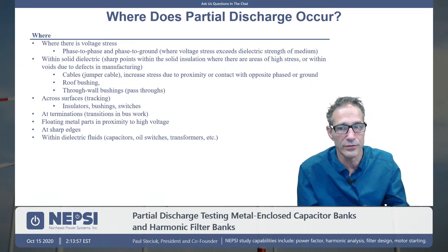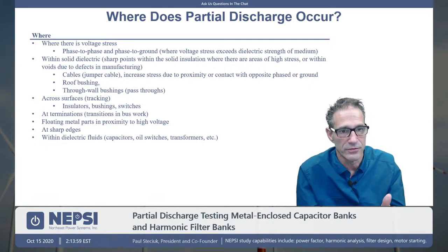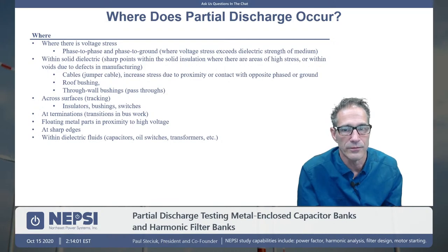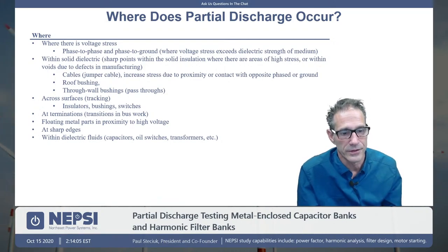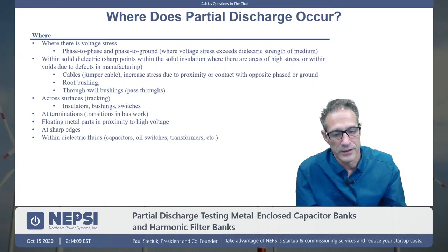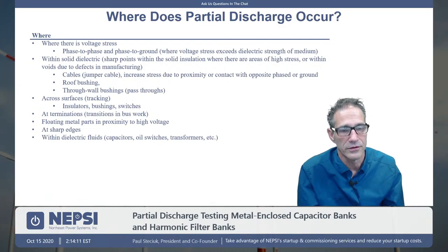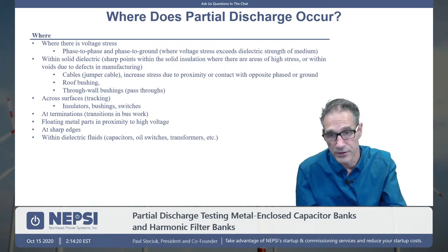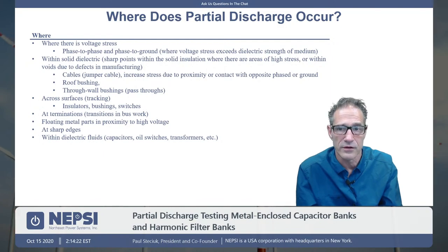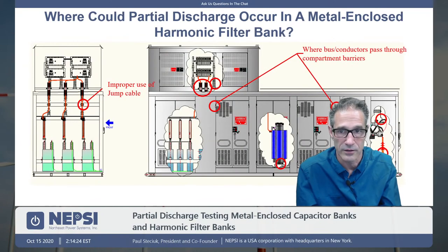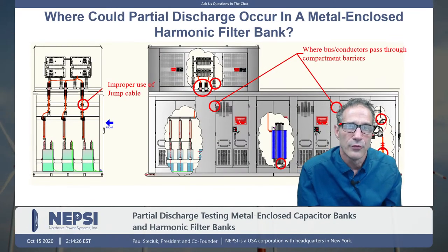And over time, you get carbon buildup and it can flash over at that location. You also get it at terminations or in transitions of bus work, where you're going from one bus structure to a different bus structure. Floating metal parts up in the high voltage region that are not properly secured to the high voltage component can result in partial discharge, and in time it will fail the insulation in that region. And then also within the dielectric fluids themselves, if you have floating metallic parts and things like that.